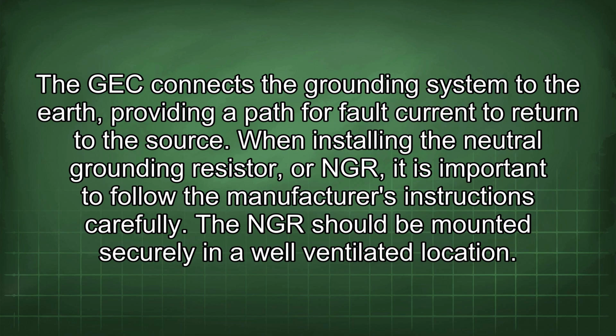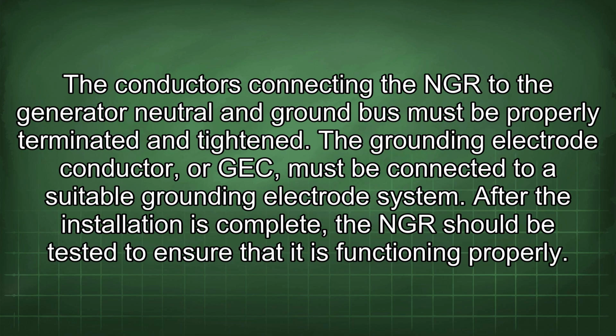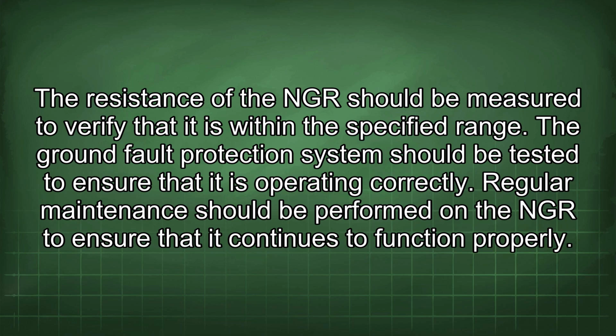When installing the neutral grounding resistor, or NGR, it is important to follow the manufacturer's instructions carefully. The NGR should be mounted securely in a well-ventilated location. The conductors connecting the NGR to the generator neutral and ground bus must be properly terminated and tightened. The grounding electrode conductor, or GEC, must be connected to a suitable grounding electrode system. After the installation is complete, the NGR should be tested to ensure that it is functioning properly. The resistance of the NGR should be measured to verify that it is within the specified range. The ground fault protection system should be tested to ensure that it is operating correctly.